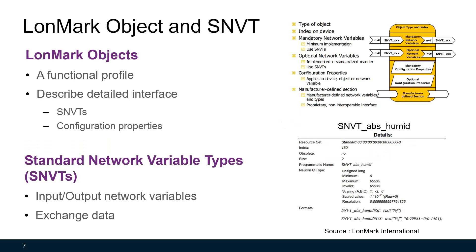Key concepts in LonWorks are LonMark objects and standard network variable types, or SNVTs. LonMark objects are a collection of network variables, configuration properties, and associated behavior. They define standard formats and semantics for how information is exchanged between LON devices on a LonWorks platform. SNVTs are input-output network variables used in LonWorks, and they are directional — either network variable inputs or network variable outputs. LON devices communicate with each other using SNVTs, and an example of an absolute humidity network variable input SNVT is shown here.